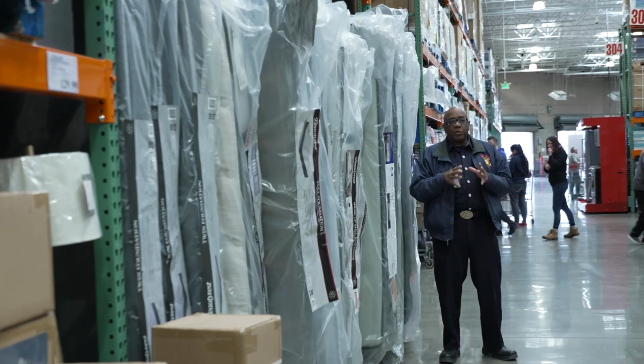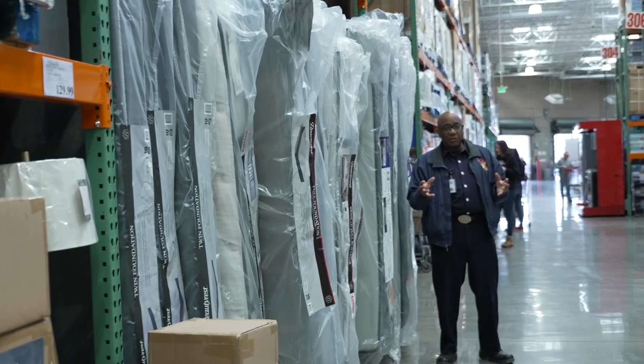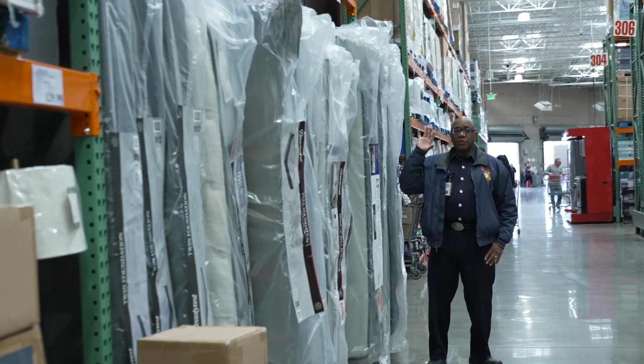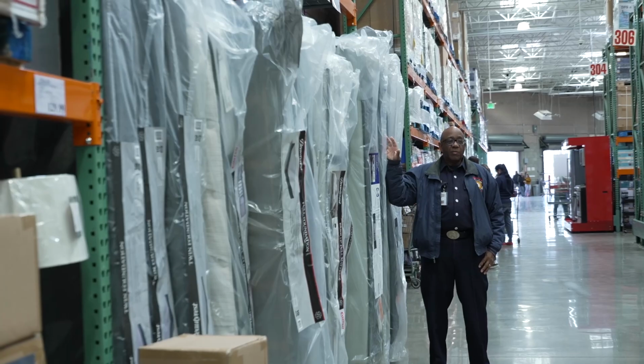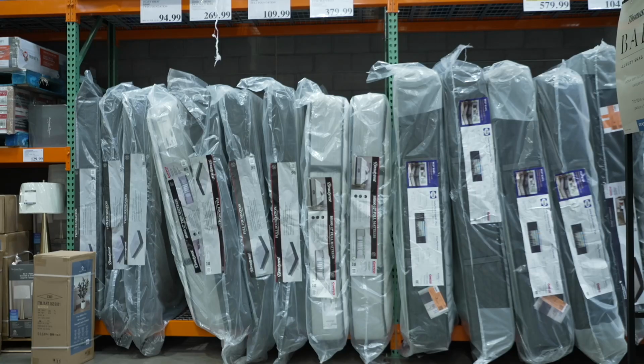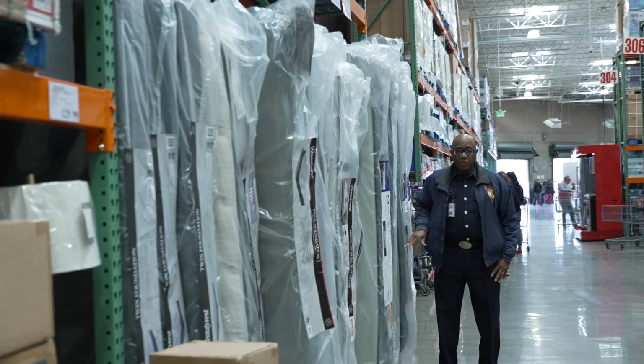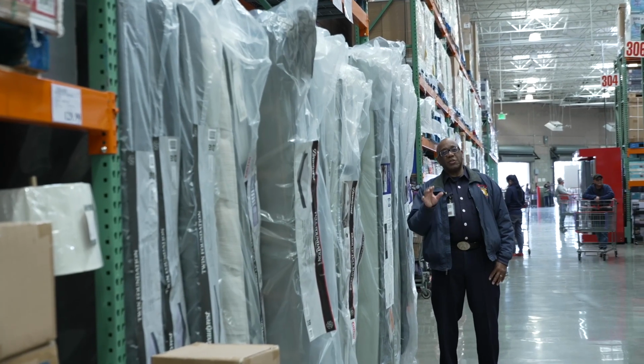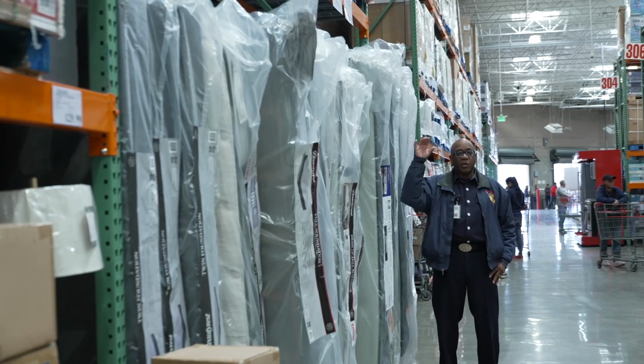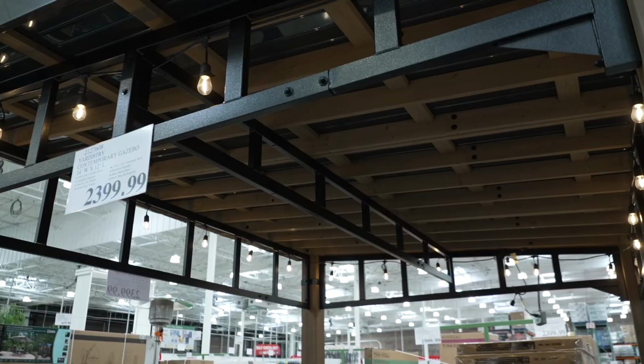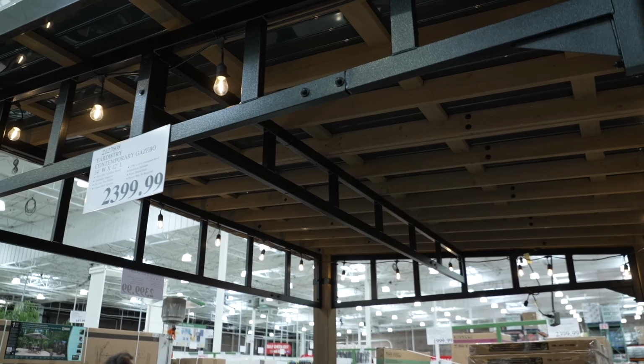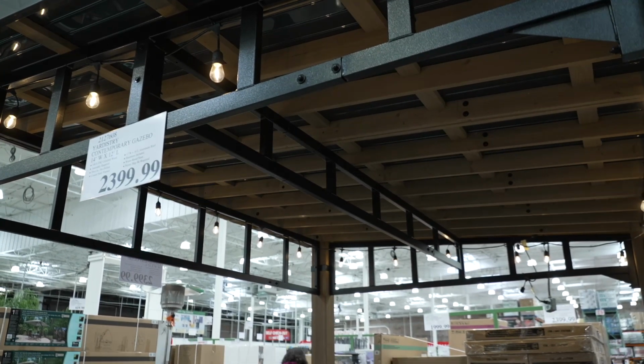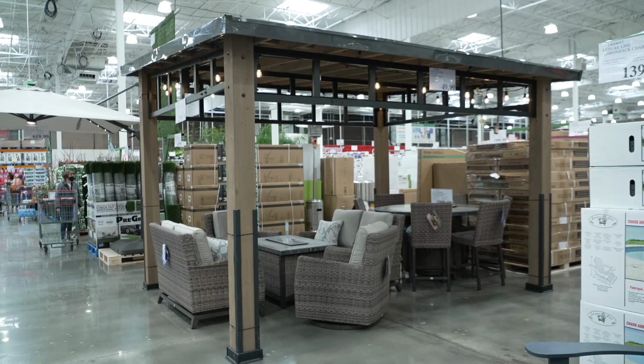So in the mercantile, what you're going to find is things that you might think are a hazard that really aren't. In this particular case, this particular mercantile is selling mattresses. Perfectly fine. Notice they're in a vertical configuration so that water can get between the mattresses. What you're going to find in some mercantile, they're going to put them in a horizontal configuration, which is not appropriate with mattresses, especially when you start stacking them 10 and 12 high. All right, here's an example of a gazebo that's set up to display product, and you notice that it's also obstructing your sprinklers from the combustibles underneath.